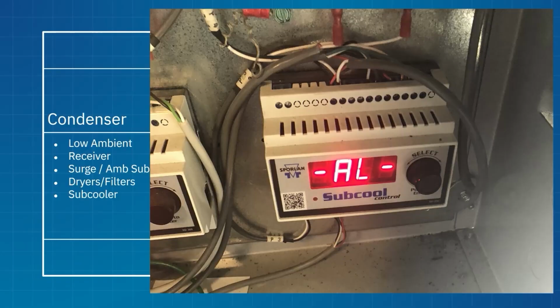So we're talking about this version, right? But to Christian's point, it doesn't have to be this. Any EMS system that can drive an electronic valve can do this. We could have an S3C doing this. There's no reason why we can't. We can have a 521, we can have a 1081, we can have Emerson's valve drivers, KE2's got a valve driver. Everybody's making one, right? As long as it can read pressure and temperature and control the valve, it could be here. So anyway, the subcooler control, we're not gonna go through that in depth today. Just know that there are many versions that can do this. Any valve controller can do this. This is just the one that's most common for that particular customer, right?